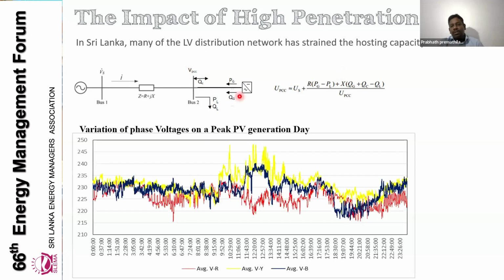These are some measurements we obtained. Up to around 9 a.m., normally the voltages in the 3 phases are in the same situation. But after 9 or 10, the phase voltages vary, depending on the generation. You can see some phases increasing, some phases reducing. If there is any single phase solar PV system, that phase voltage is increasing. This is the first biggest challenge in the LV network that we are facing at the moment.